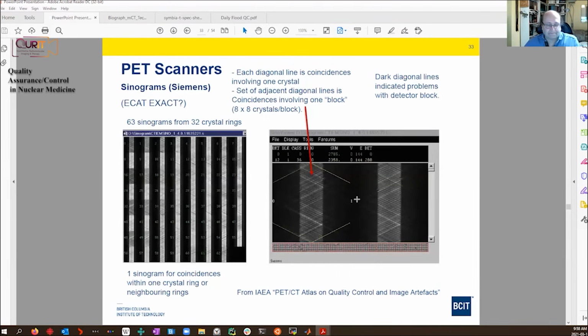Another way of looking at quality control daily is by looking at sinograms acquired from a uniform source. So a diagonal line in a PET sinogram is all the coincidences between one particular detector and the other detectors, or detector blocks, if we want to look at it on the bigger scale. We should see fairly uniform count density; again, this is cleaned up by the normalization scan. But if we see an area with very low count density in a diagonal line, that's a clue that there's a problem with a particular detector block.